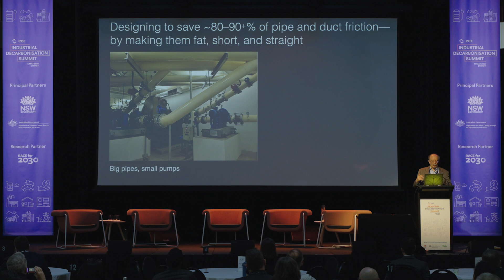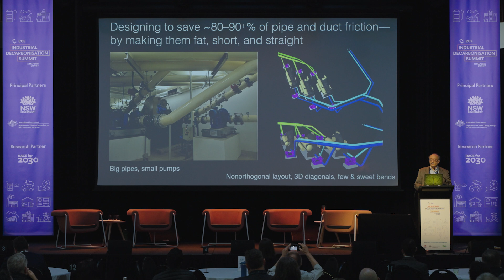There go 4 elbows. And to get rid of the remaining elbows and their friction, we lay out the pipes first, then the equipment, not the other way around. So the 10 chillers that used to be in a neat row get staggered until the elbows go away. We lay out supply pipes as if they were drains. We bend minds, not pipes. And thus our colleague Peter Rumsey's retrofit of the Oakland Museum's condenser water pumping loop cut the pumping energy by 3/4 with a 2 or 3 month payback, a retrofit. And it eliminated 15 pumps that will never again waste energy and maintenance costs.